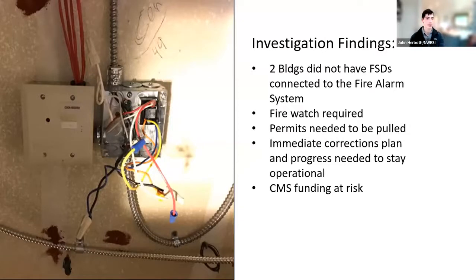It's the type of situation where we're like, okay, this is really bad. But as we kept going and noticed whole floors of FSDs failed, we realized there was a bigger problem. We found that out by tripping the fire alarm system, tripping some duct and area smoke detectors. We found that 2 of those 3 buildings, the newer sections, did not have the fire smoke damper relays tied into the fire alarm system. The old relays were found in place and new relays were not when they swapped out the brains of the fire alarm control panel. We immediately had to take our facility contact, our maintenance lead, and shut the door to talk to them, because the fire alarm maintenance provider was also on site doing their own testing, and I notified them as well.